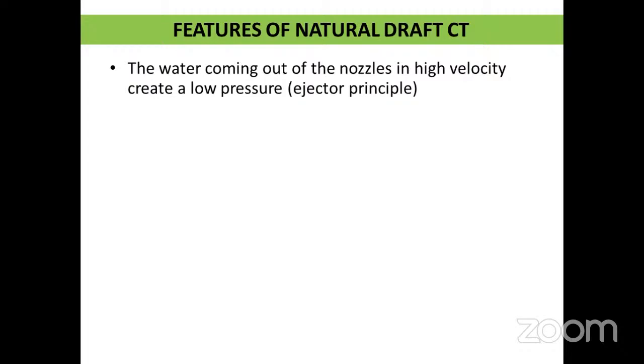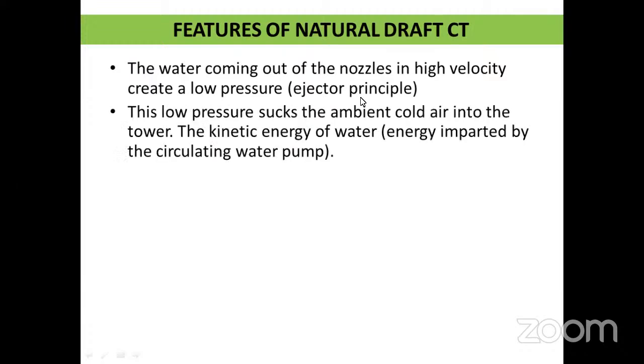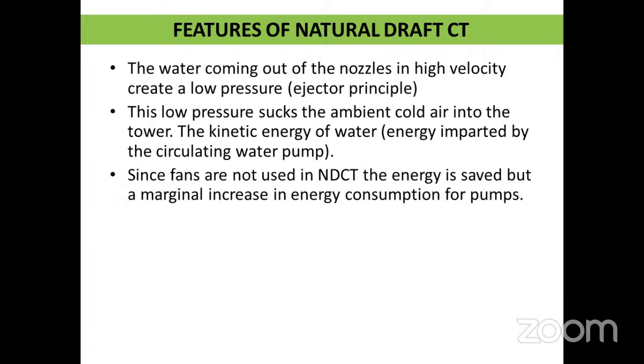Okay, sir. Sir, any doubts, sir? This is an important point, sir. The low pressure sucks the ambient cold air into the tower. The kinetic energy of water is the energy imparted by the circulating water pump. Since fans are not used in NDCT, the energy is saved, but there is a marginal increase in energy consumption for pumps. Even in mechanical draft, that is forced draft cooling towers, there will be water pumps. Here also water pumps will be there. But this one, natural draft cooling tower, we'll have to.